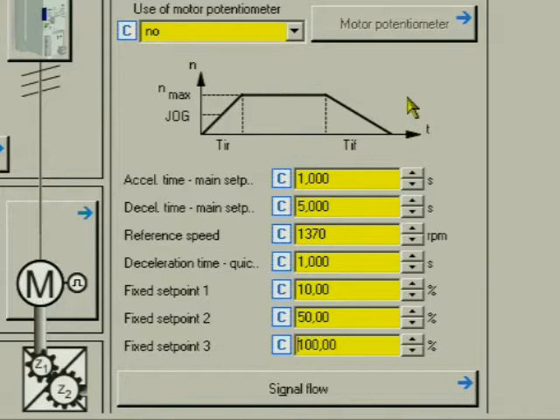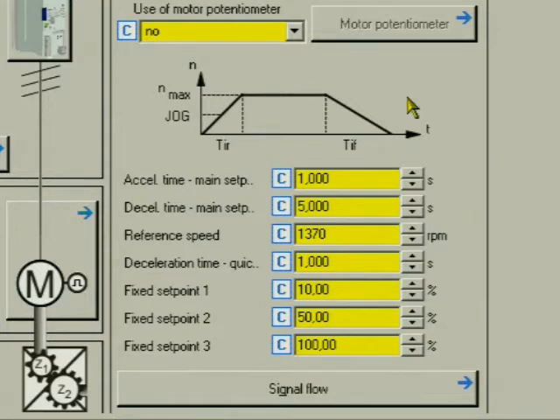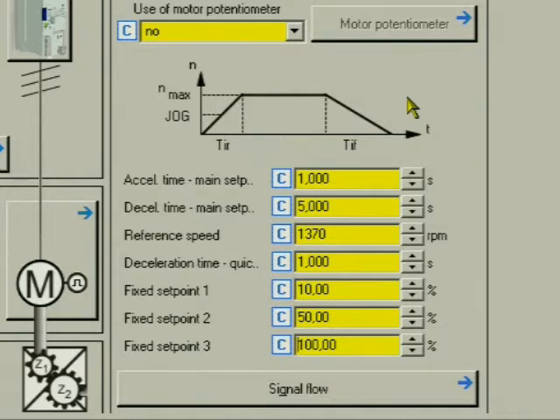Fixed setpoint 3 to 100%, this corresponds to maximum speed. The fixed setpoints relate to the reference speed, which means fixed setpoint 1 corresponds to approximately 137 revolutions per minute. Fixed setpoint 2 corresponds to approximately 685 revolutions per minute. Fixed setpoint 3 corresponds to approximately 1370 revolutions per minute.